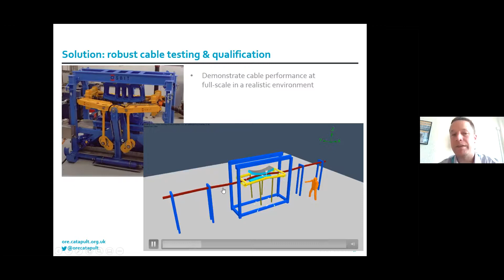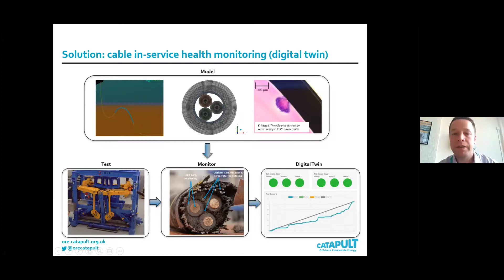So we take all the models I talked about, the global model as well as a local model, as well as models of things like insulation, water treeing, thermal degradation, fatigue models. You take test data to validate those models to make sure that they're sensible and they characterize what's really going to happen. And then you make sure you put sensors on your real system. So there's many ways of monitoring the cable through strain, vibration, temperature, and electrical monitoring. And you integrate all this together, and you use that then to track your cable performance. So how's it fatiguing? Is it behaving as we expect? And ultimately, 25 years into the life, you can ask, well, do we need to replace the cable, or can we run it for another 10 years?